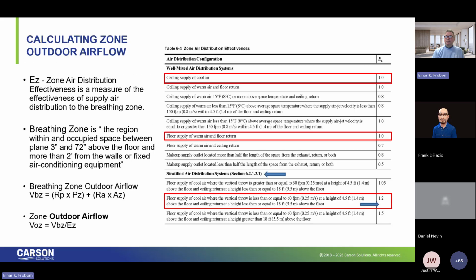So in terms of energy efficiency, here's that chart that I was referencing for those that aren't familiar. In ASHRAE 62.1, up here is the mixed air system component, and down here is the displacement or stratified air. But the key point is that's a finite list, while possible ventilation designs are limitless. ASHRAE recognized that this chart has limits. So in the 2019 version, they stated you can either use the default values in the chart or you can go measure it and test it. And if you test your ventilation system, you have to do it empirically, you have to CFD model it, and you have to do it in heating and cooling.